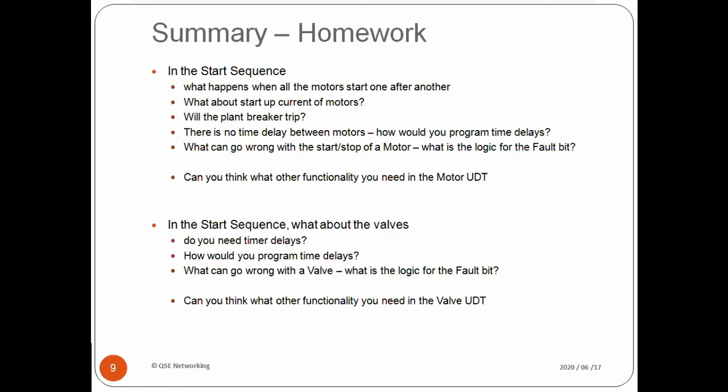So we talk about the startup currents, and yes, we'll probably trip the main incomer. So what I want you to think for yourself, how would you create a time delay between the motors starting in the sequence? Would you do it in the motor circuit or in the motor drive block, or would you do it in the sequence?